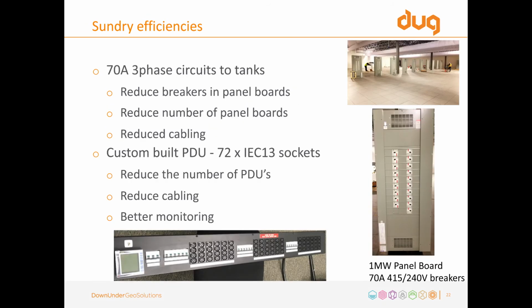A few sundry things we did, all the little details. We're running 70 amp 3-phase circuits to each tank or pair of tanks. This reduces copper and breakers in the panel boards, because a 70 amp breaker is the same physical size as a 60 amp, a 32 amp, or a 16 amp breaker, but you get much more power through. So this reduces the number of panel boards, reduces cabling, all massively reduced just by deciding to go high power. We run 3-phase, 70 amps, 415 volts 3-phase, 240 volts a phase to each tank.